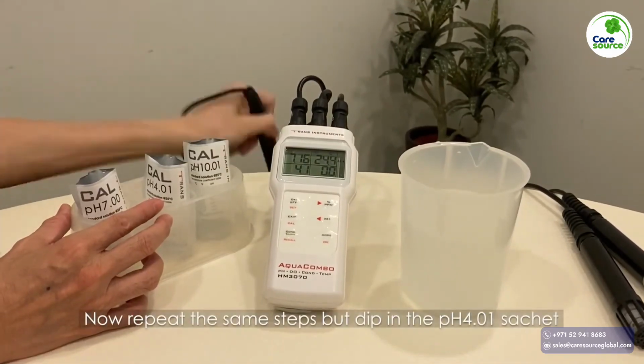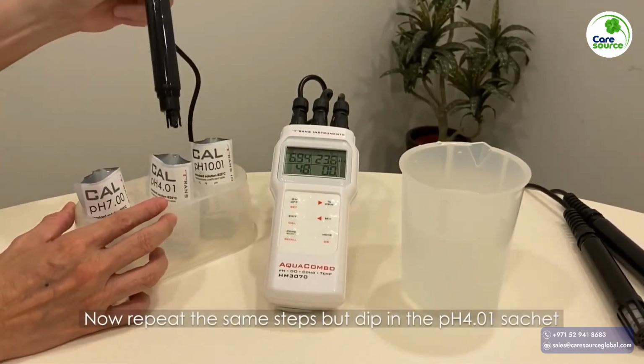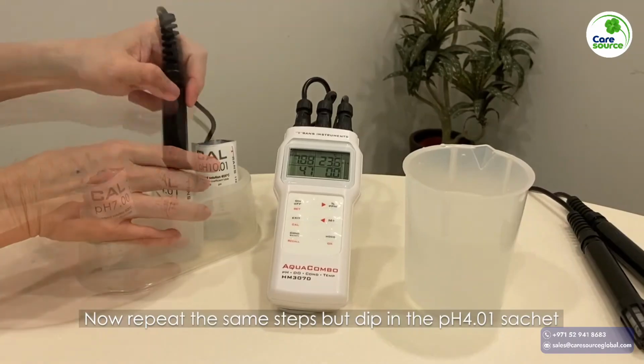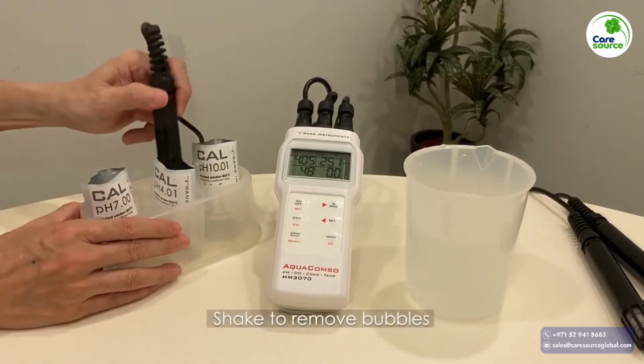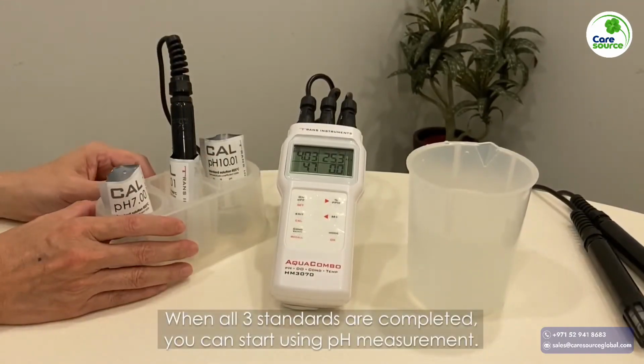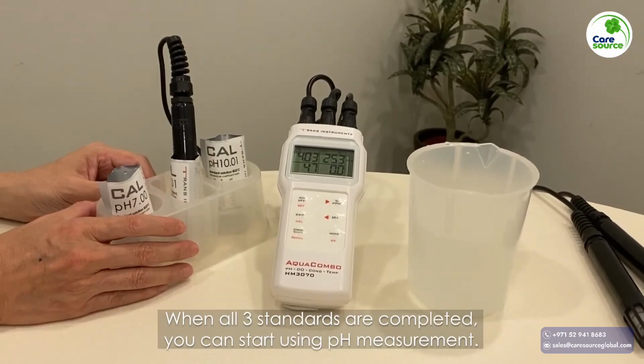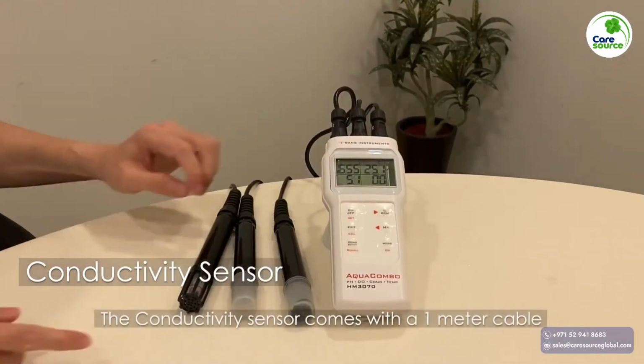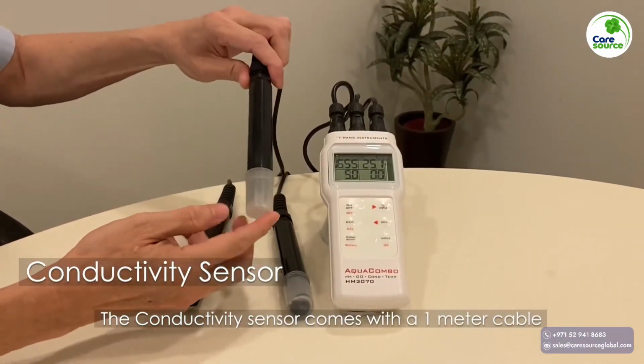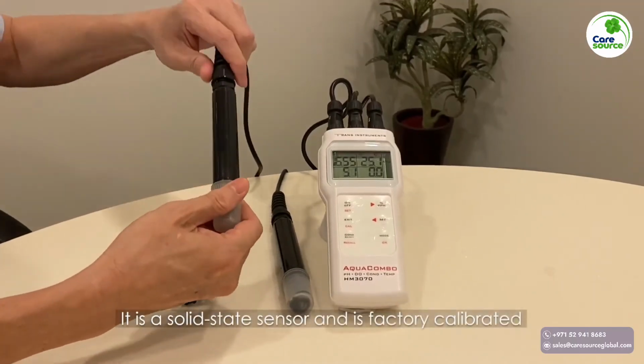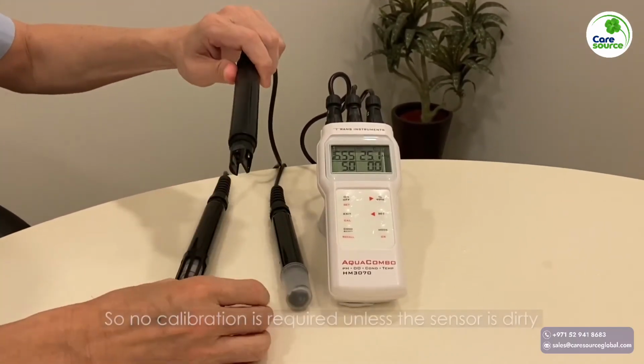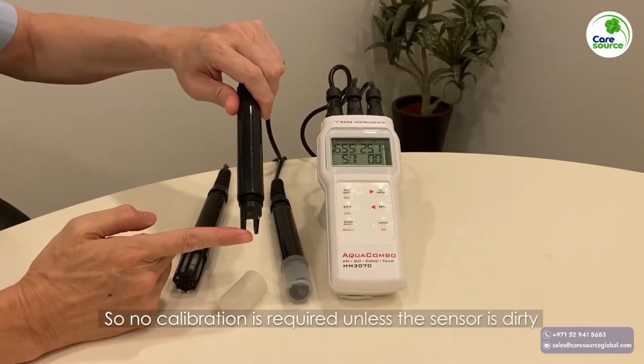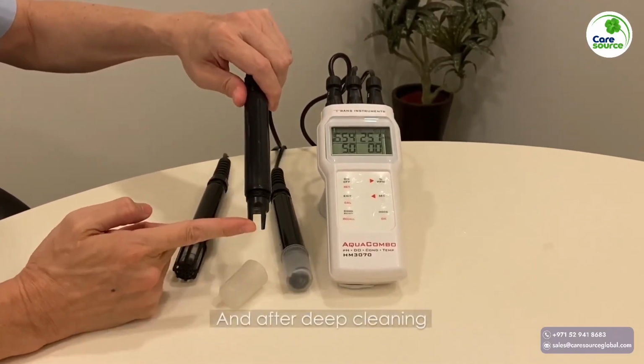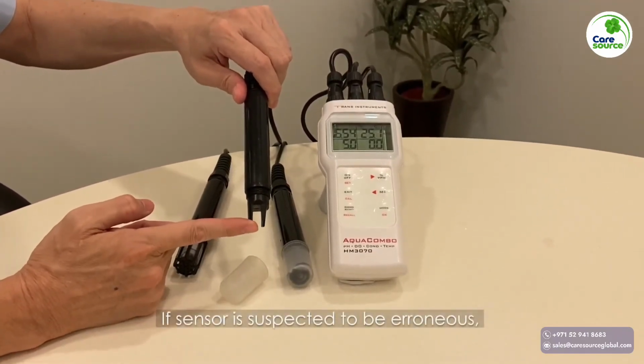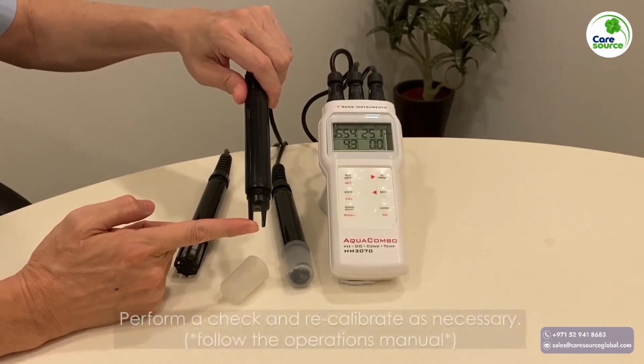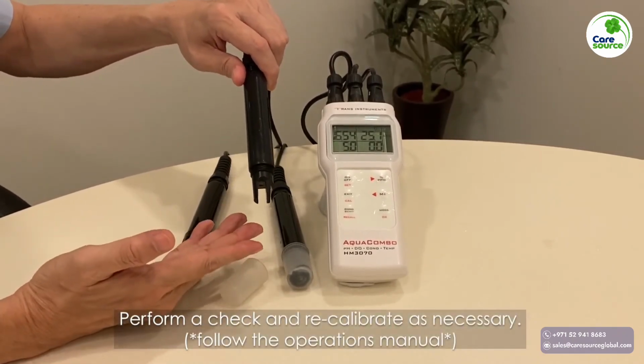Now repeat the same steps but dip in the pH 4.01 sachet. Shake to remove bubbles. When all three standards are complete, you can start using the pH measurement. The conductivity sensor comes in a 1 meter cable. It's a solid state sensor and is factory calibrated, so no calibration is required unless the sensor is dirty and after deep cleaning. If the sensor is suspected to be erroneous, perform a check and recalibrate as necessary.